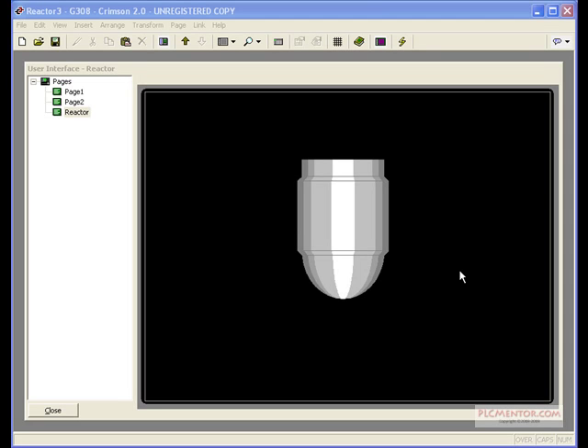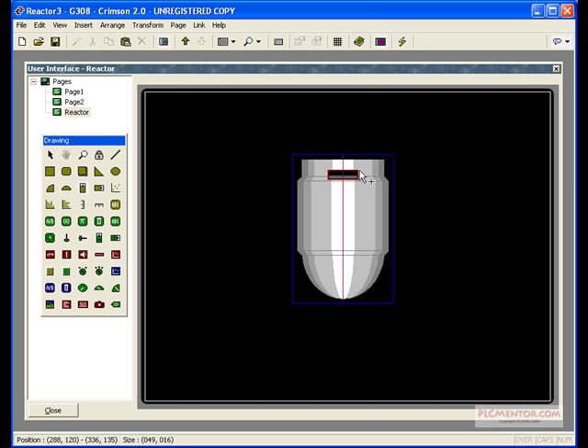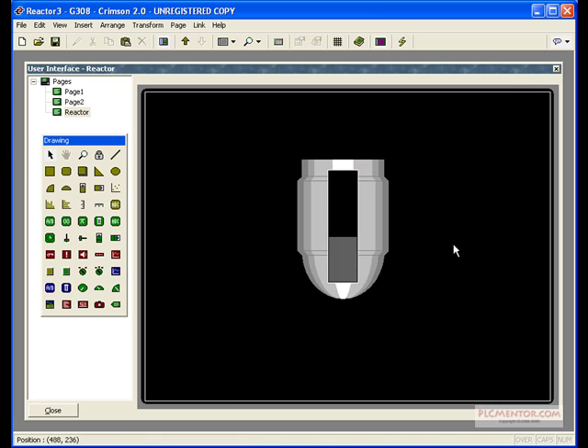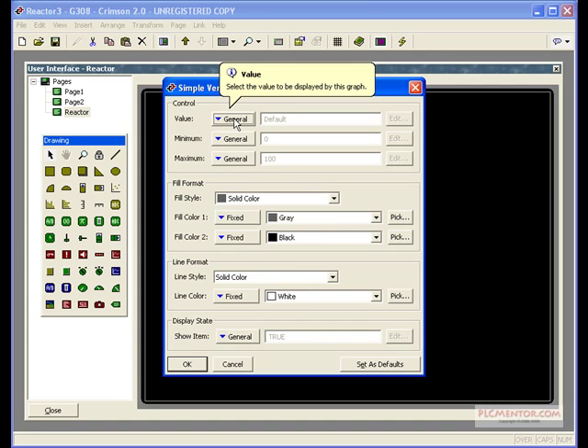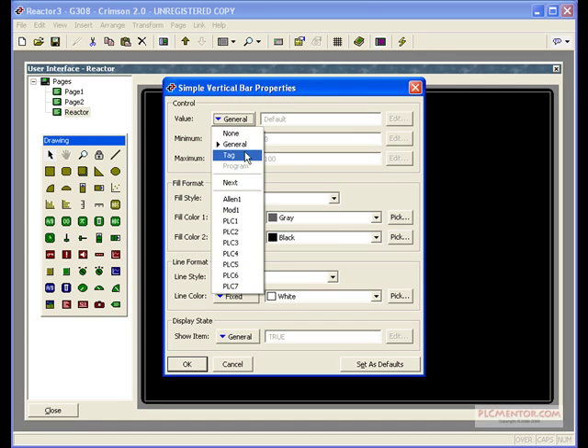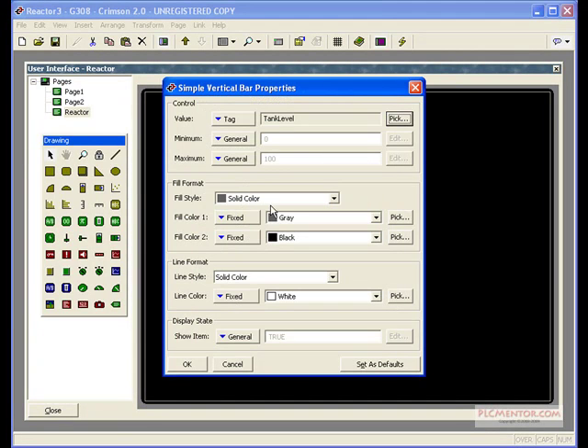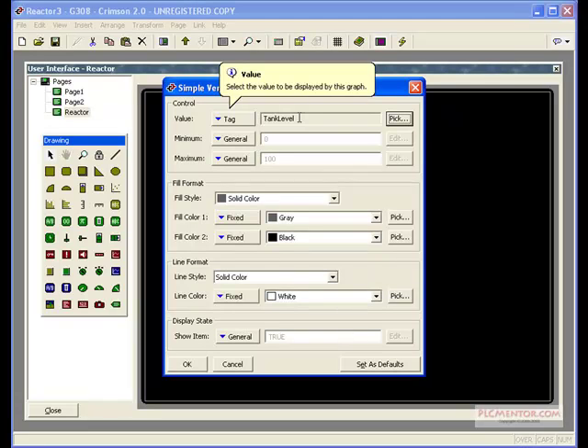Let's make a way to display our tank level. We'll bring up our Toolbar, select a Simple Vertical Bar, and draw that right over the top of our tank. Now, we need to assign that a tag. We'll bring up the properties of it and the Control Value. We'll select Tank Level. This is an integer tag that I created previously and assigned a script to, so we can simulate our tank filling.